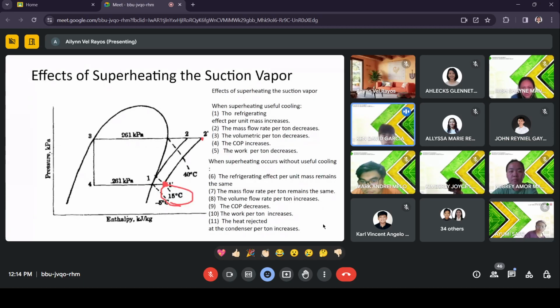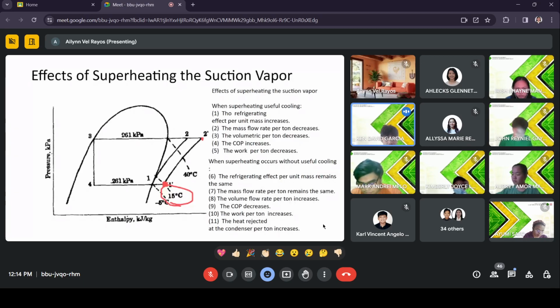Effects of superheating the suction vapor. When superheating useful cooling, the refrigerating effect per unit mass increases. The mass flow rate per ton decreases. The volumetric per ton decreases. The COP increases. The work per ton decreases.